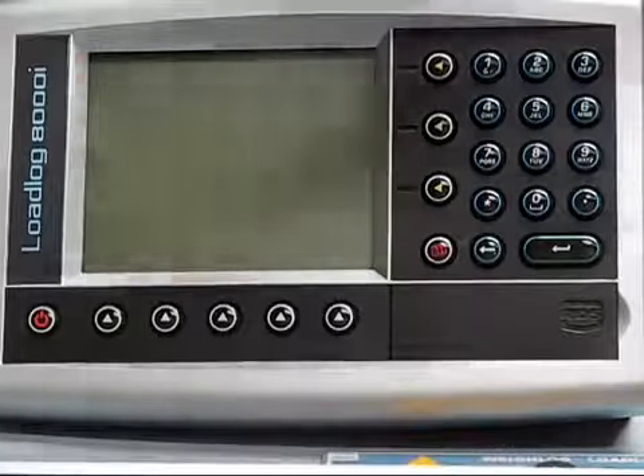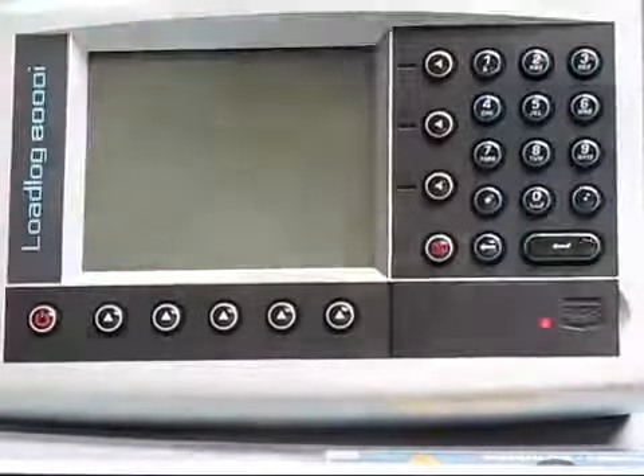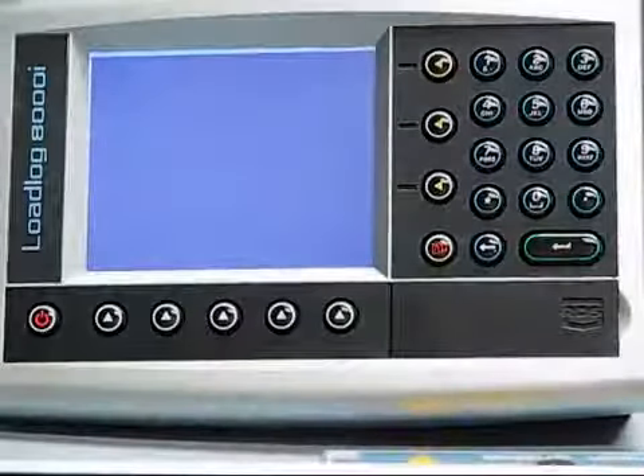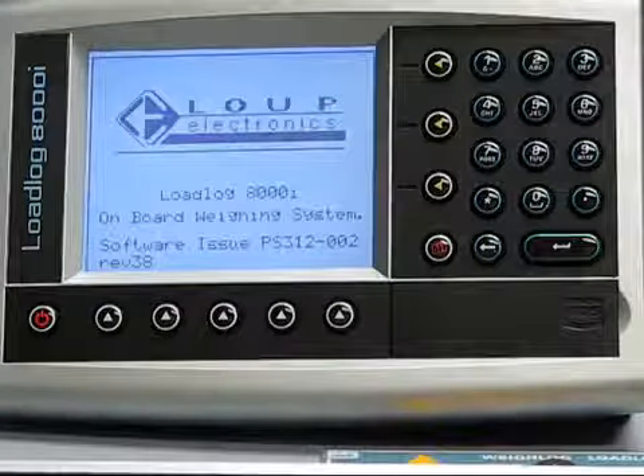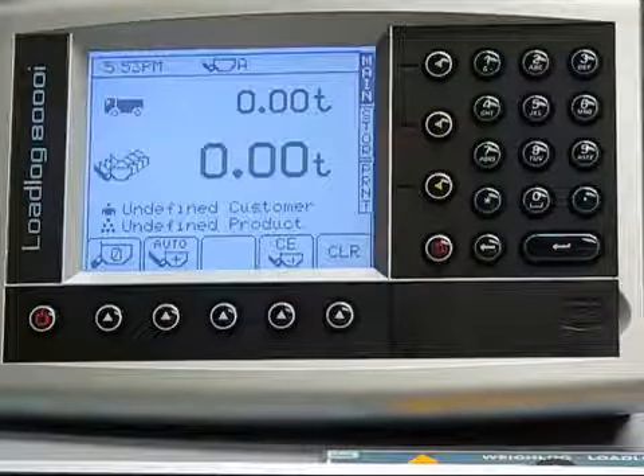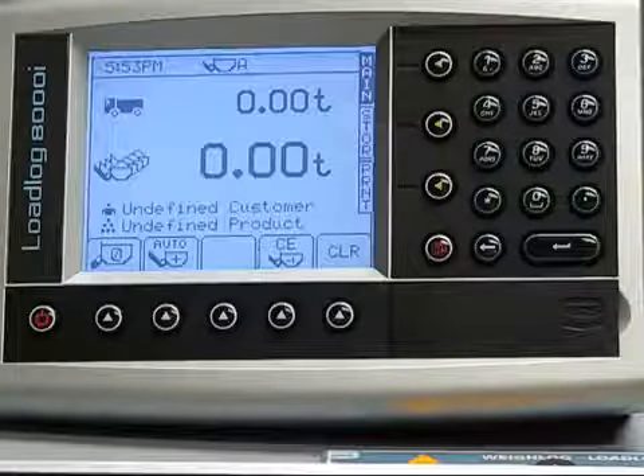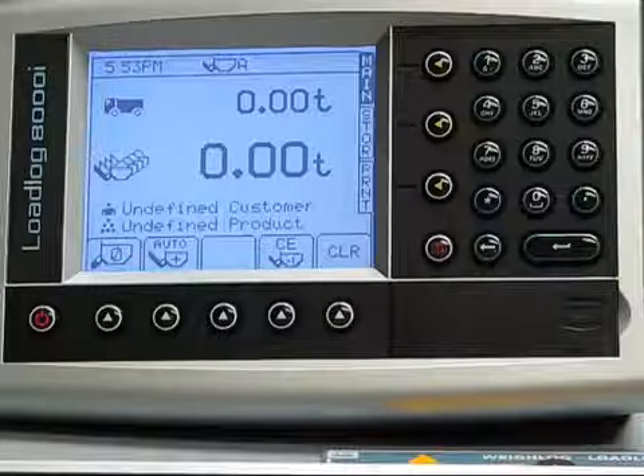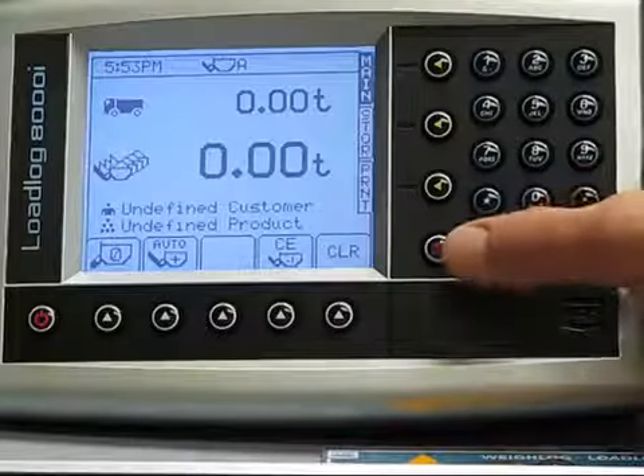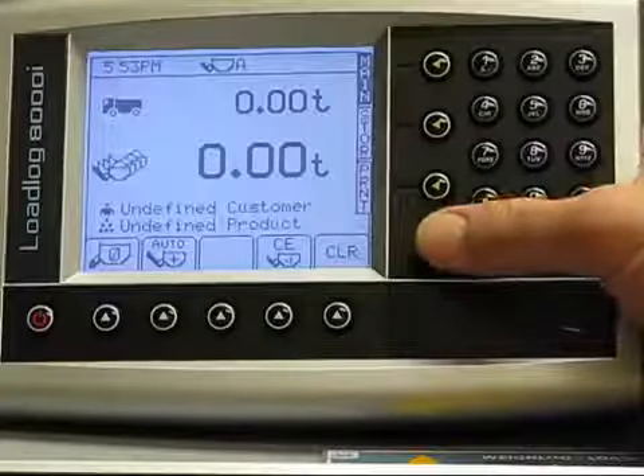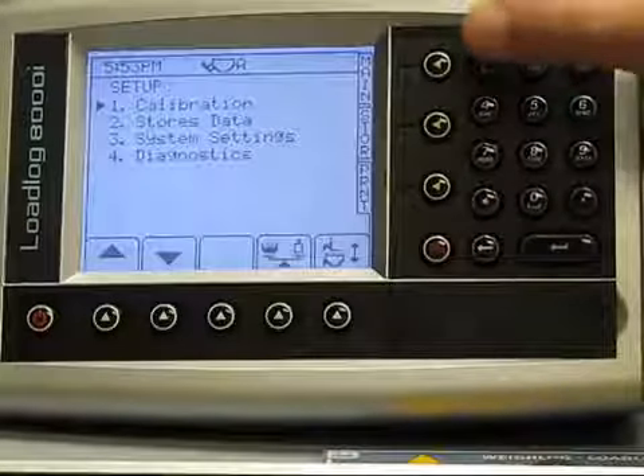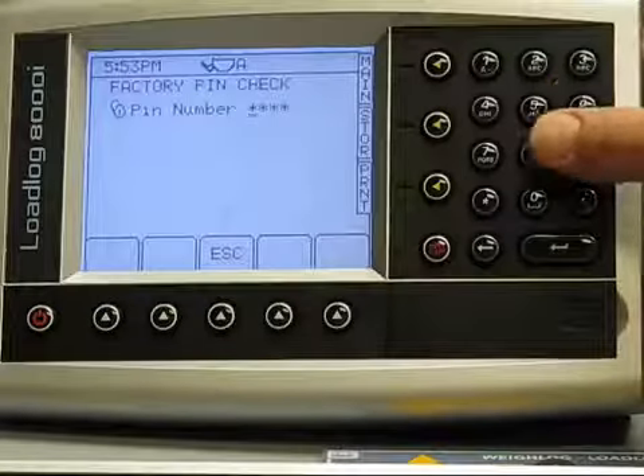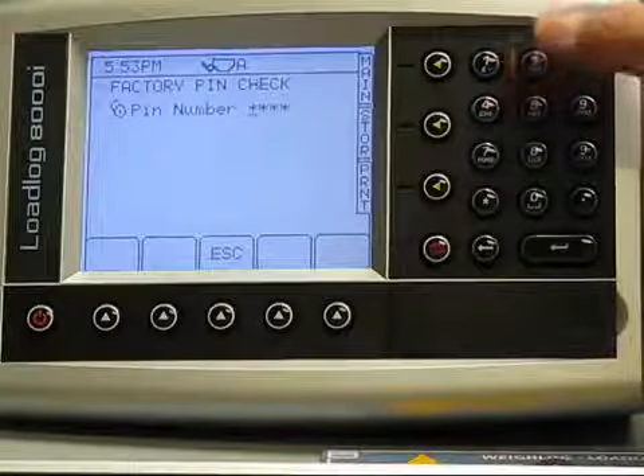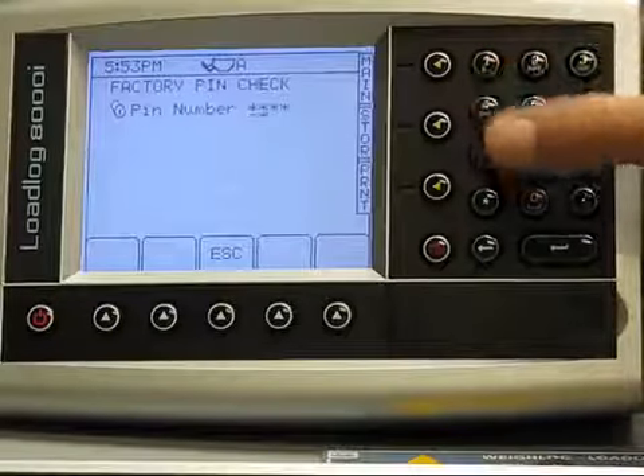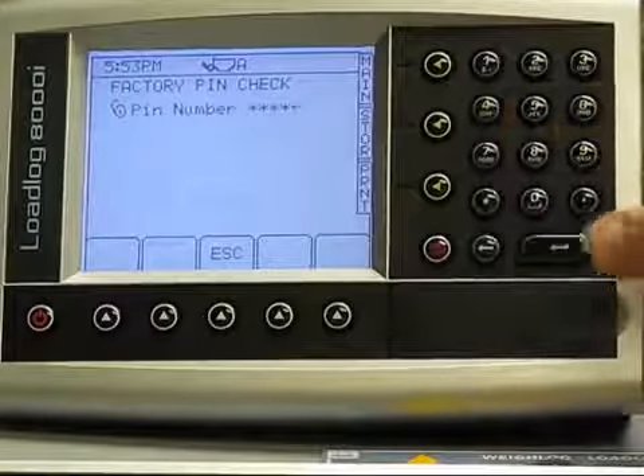This video is for the calibration of an 800 or an 8000 I load log. In order to enter the calibration, you must press the menu key, the red key, select number 1 for calibration, enter the factory pin. The default factory pin is 4084. Press the enter key, which is the green key.